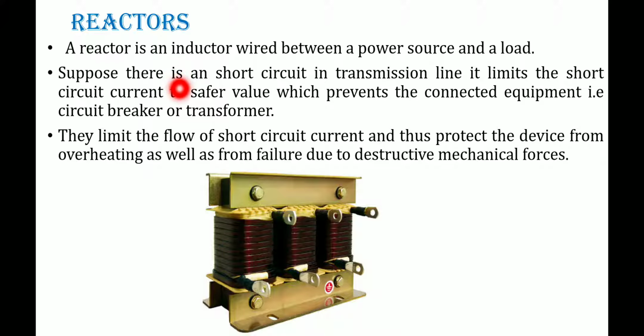Suppose a short circuit occurs in a transmission line, then what happens? The line reactor limits that short circuit current to a safer value, which prevents damage to the connected equipment. This is completely avoided with the help of these line reactors.